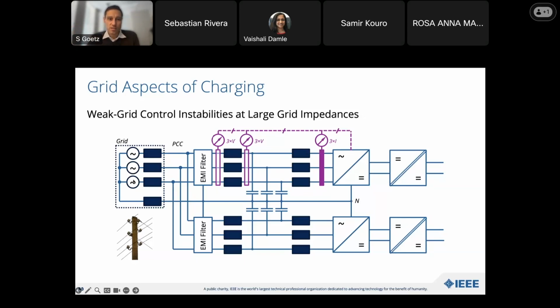The consequence is that the impedance gets higher, and you get interaction between your filter, for example a second order LCL filter, with the grid impedance. That can pull your resonances to pretty low frequencies, and as soon as they reach into the control bandwidth of your grid inverter or rectifier, you can run into terrible oscillations. Next, you get positive feedback.